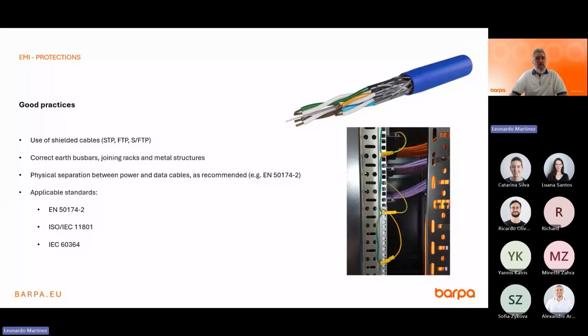So first of all, what would be good practices when we are having an installation in a potential high EMI environment? The good pattern will be to use shielded cables, use shielded solutions, and use good earth bus bars for joining racks to metal structures, for earthing and bonding.